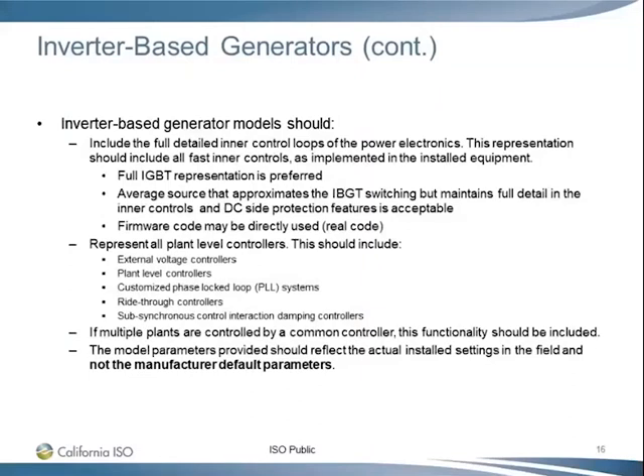So you need to model the full detailed inner control loop of the power electronics. The full IGBT representation is preferred, but the average representation is also acceptable, as long as it keeps the detail in the inner control loop and DC side protection. And we highly recommend using real code. That is the firmware code directly being packed into that black box model. Also include all plant level controllers, not just the inverter control. We require plant level controllers to be included. They could include external voltage controllers, any customized phase lock loop system, and ride-through controllers. And if you have sub-synchronous control interaction damping controllers, include them. Basically everything inside your plant that's doing some control function, you should have in the model.